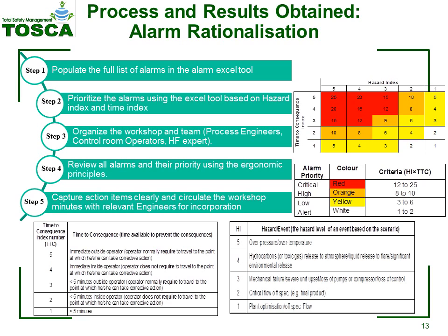Moreover, an Excel tool was developed to assist the designers in selection of alarm priorities based on the related hazards and the time before the consequences. This matrix structure helps the process engineering team to select the right priority for the alarm in accordance with best practices.